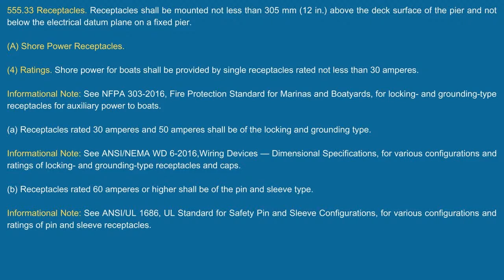Yeah, and that's a good point, James. In layman's terms for all the people watching, what we try to do is selectively coordinate this for the safest install possible. So what we're doing is 100 milliamps upstream on the feeder, then that's going to a 30 milliamp, and then we're going from the 30 milliamp to the 10 milliamp. That's right.